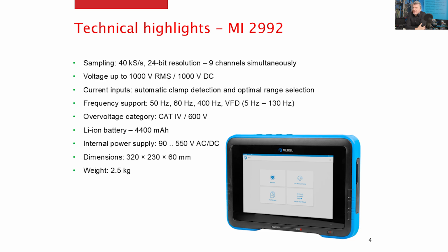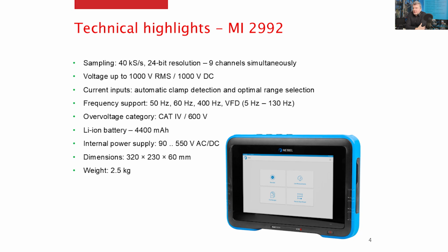The internal backup is a Li-ion battery with 4.4 ampere hours, and backup takes about 4 to 5 hours, depending on the battery state and the charging. When you connect to the external supply, the battery is automatically charged. The internal supply is from 90 up to 550 volts, AC or DC. So you can connect directly phase-to-phase voltage or phase-to-line voltage, or connect directly to an outlet. Because of the biggest screen in the class, the total size of the instrument is similar to an A4 sheet of paper, and the weight of the instrument is around 2.5 kilos.